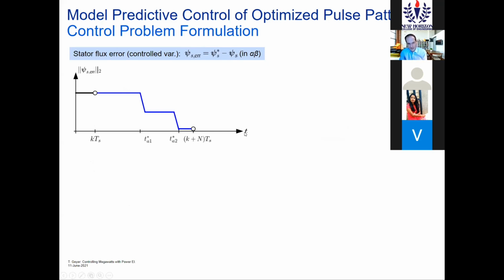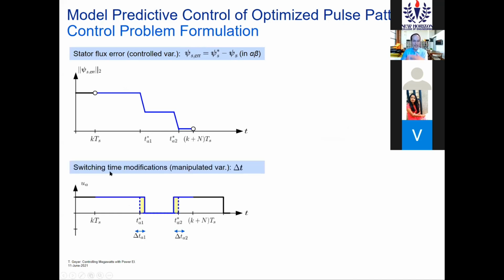Now, this is the time axis. This is where I am, and I would like to reduce this error over this interval, which is my prediction horizon. Whenever I have a switching transition coming up, for example in phase A, I can modify them, and I modify them such that I reduce this error. I want to minimize the predicted error at the end of the interval by making these modifications, while modifying my pulse pattern as little as possible.